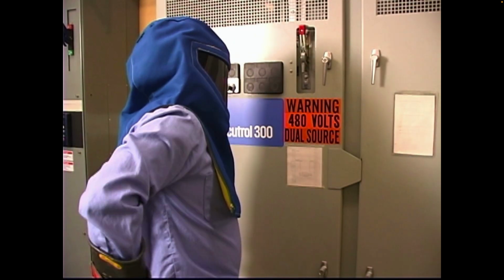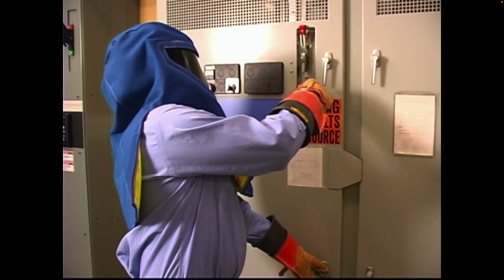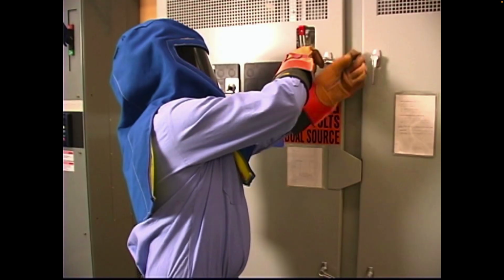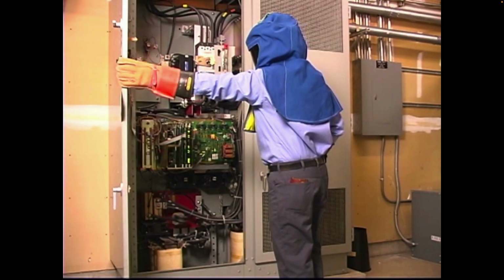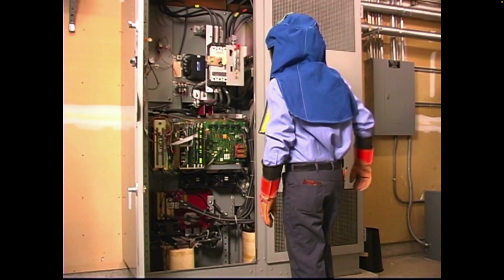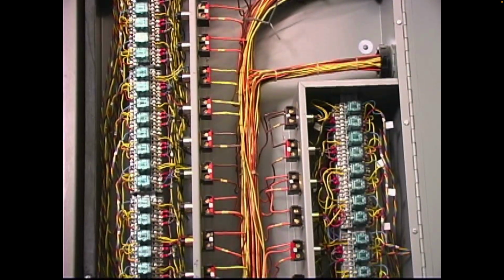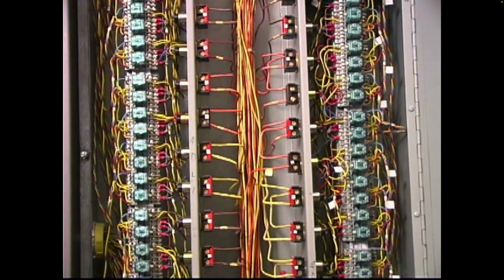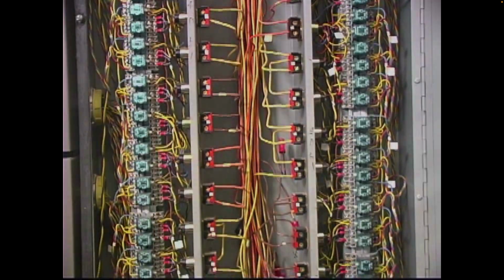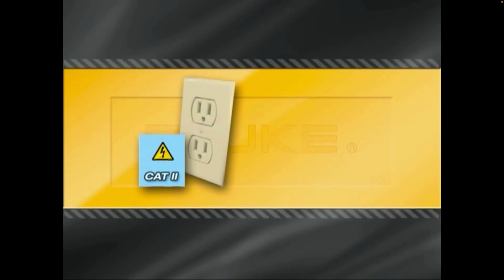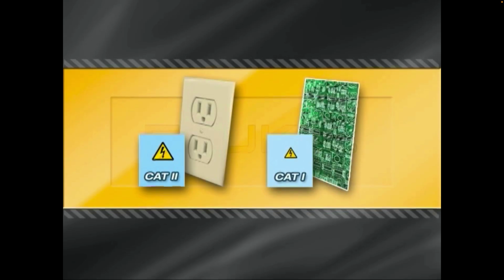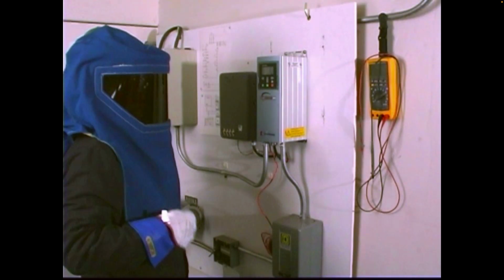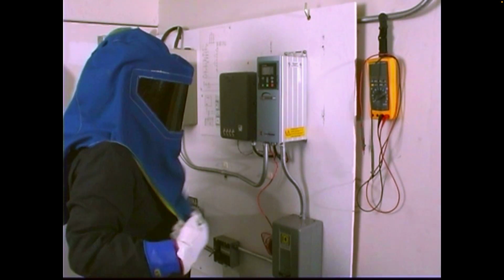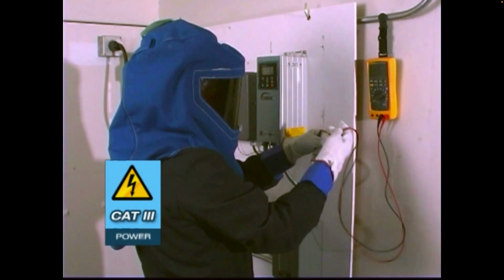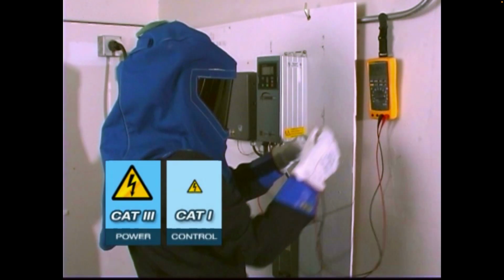Most commercial and industrial electricians work on equipment in a CAT 3 or CAT 4 environment. Many times, people may be working in a CAT 4 environment without even knowing it, and that can lead to real danger. Lower category installations usually have greater impedance, which dampens transients and helps limit the fault current that can feed an arc. CAT 2 covers the receptacle circuit level and 120-volt plug-in loads. And CAT 1 refers to protected electronic circuits. Some installed equipment may include multiple categories. This motor drive panel is CAT 3 on the 480-volt power side and CAT 1 on the control side.